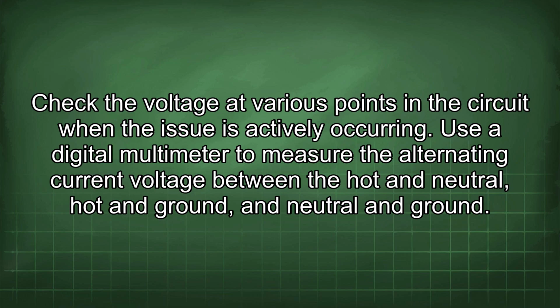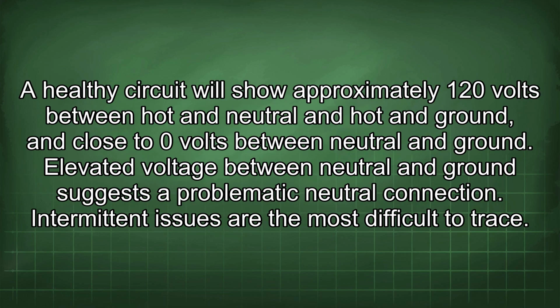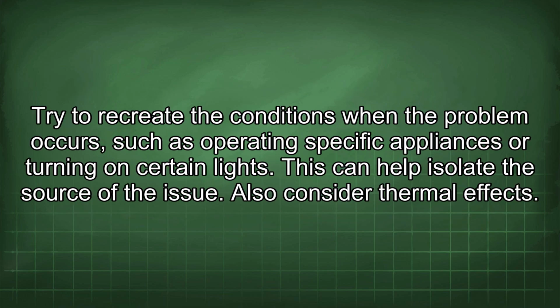Use a digital multimeter to measure the alternating current voltage between the hot and neutral, hot and ground, and neutral and ground. A healthy circuit will show approximately 120 volts between hot and neutral and hot and ground, and close to 0 volts between neutral and ground. Elevated voltage between neutral and ground suggests a problematic neutral connection. Intermittent issues are the most difficult to trace. Try to recreate the conditions when the problem occurs, such as operating specific appliances or turning on certain lights. This can help isolate the source of the issue.